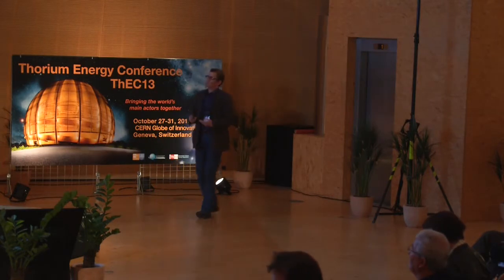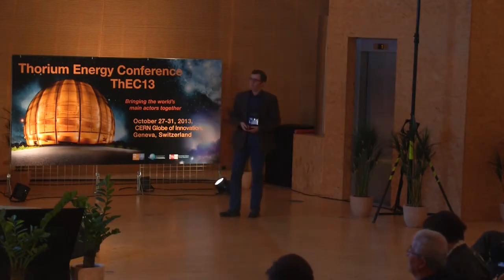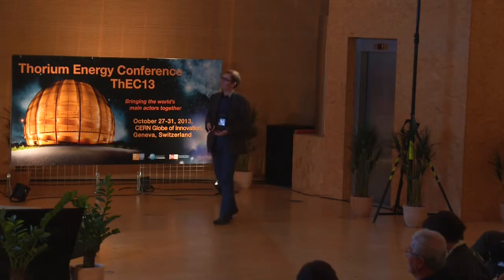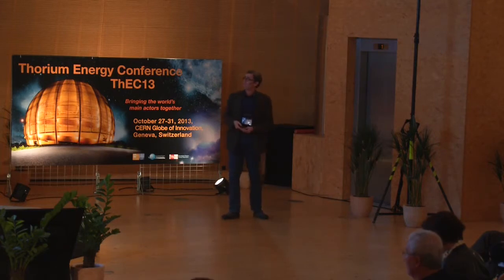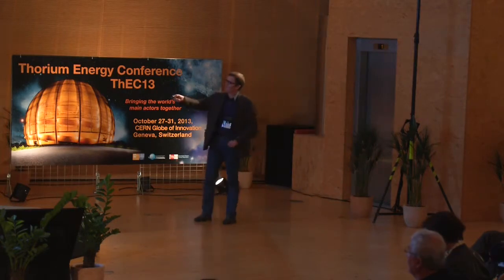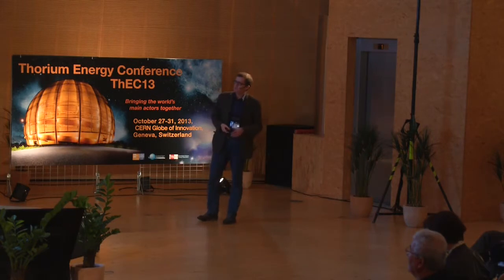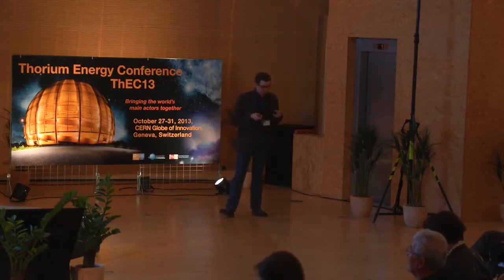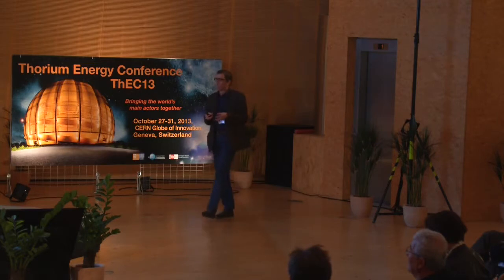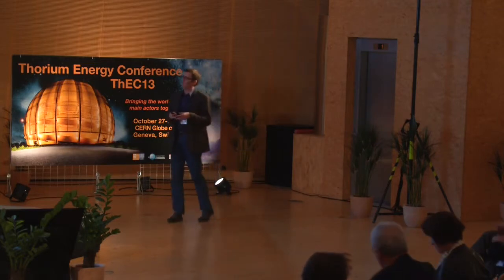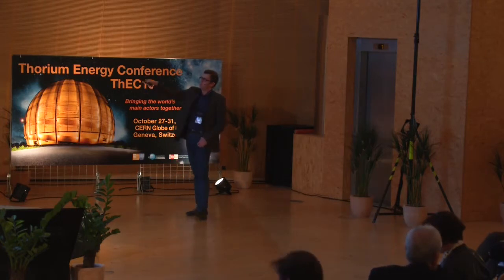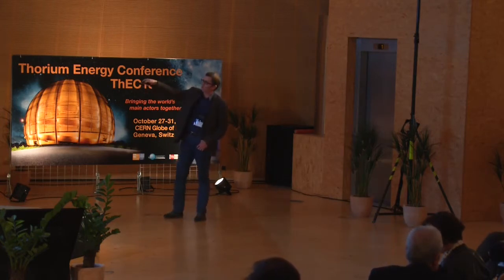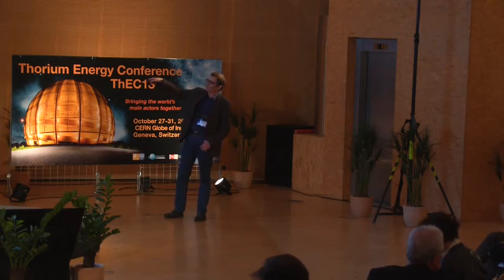From the viewpoint of safety, we can look at just two reactivity effects, Doppler effect and void effect, especially for sodium. This is the most crucial thing. But please have in mind that in a fast reactor, there are a number of reactivity effects which are probably less dependent on fuel type, and these are thermal expansion effects. So I did an illustration here and put different structures like core, control rods, diagrid, strongback vessel.